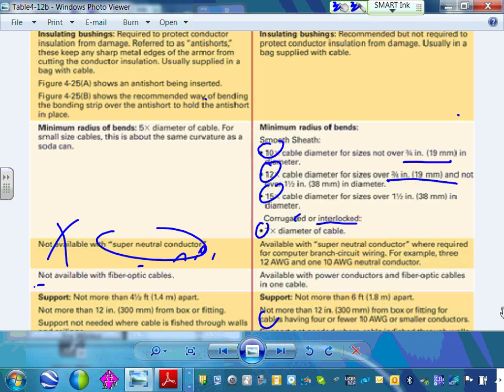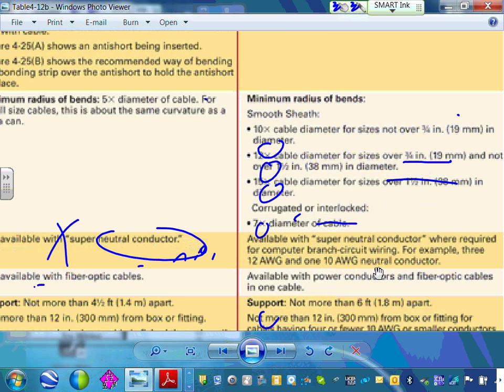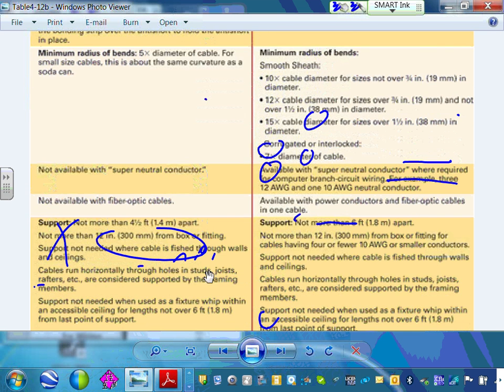Okay? And multi-neutral, you solve the harmonics in 2 ways. Either, if this is number 14, you can make this number 10. Or, if this is number 14, I have 2 of them, so I have 2 whites with them. But you're right, I think super neutral is when they oversize it, not when they multiply it. But I don't think it even comes with a neutral in every phase. So the neutral will be larger than the other conductors. Okay, so you can see where the MC cable is superior.